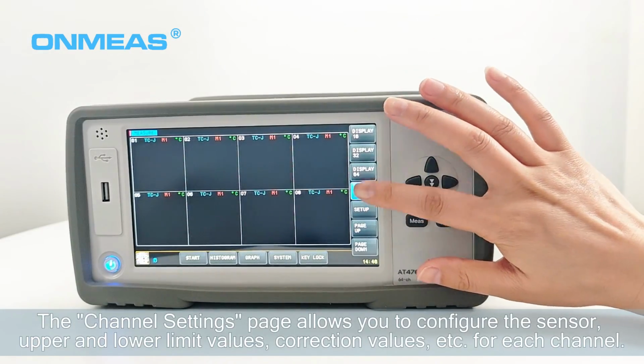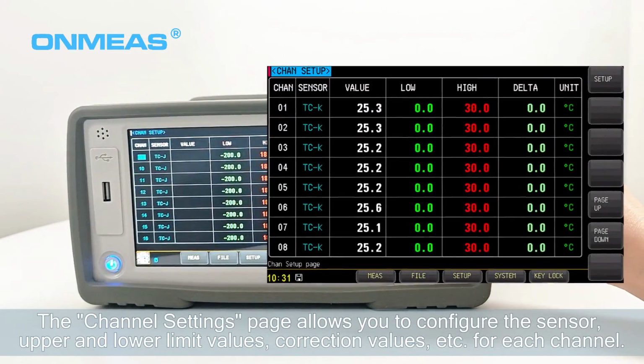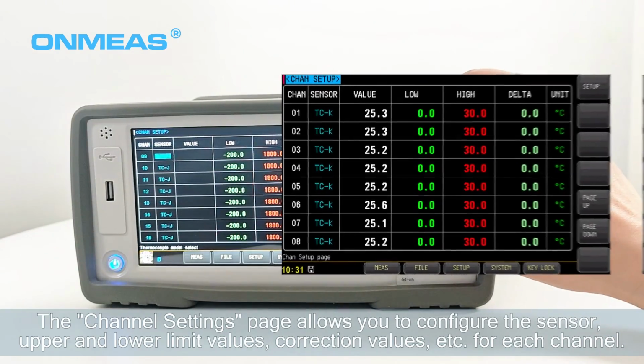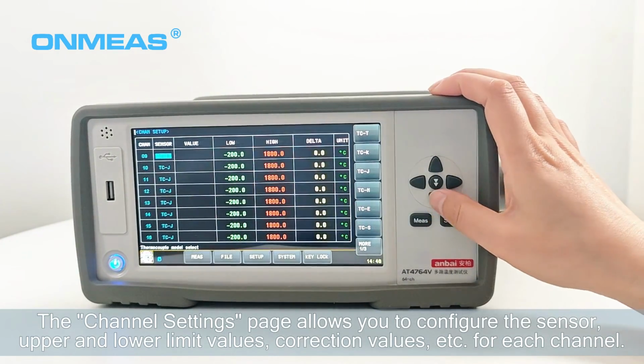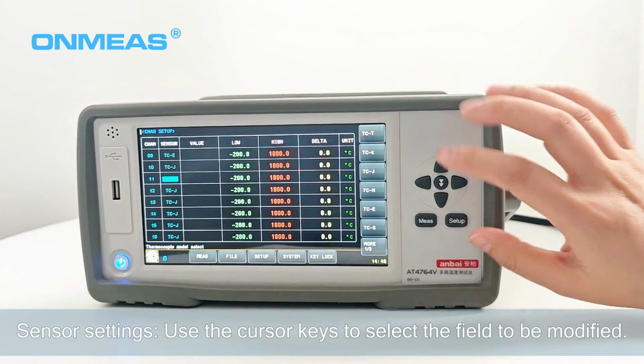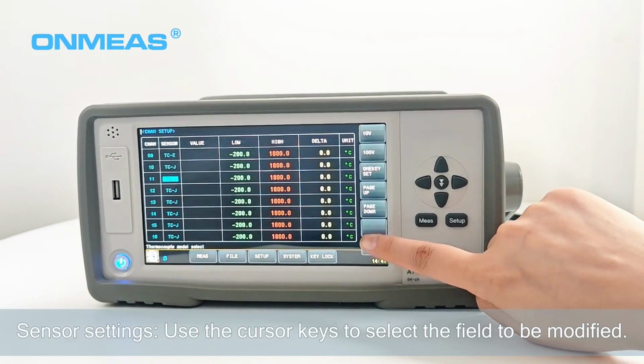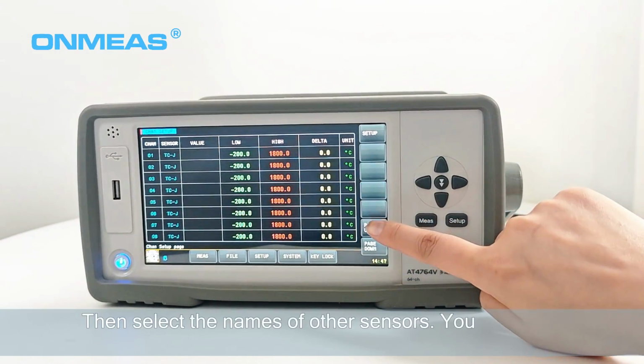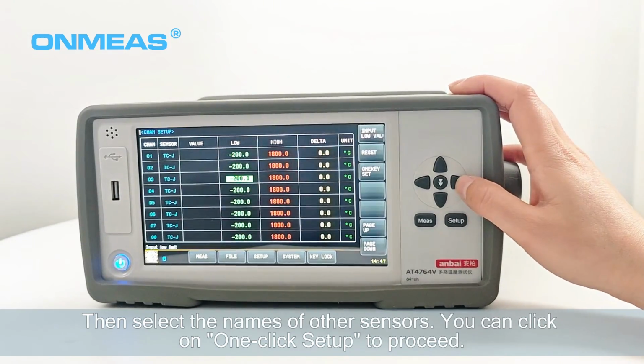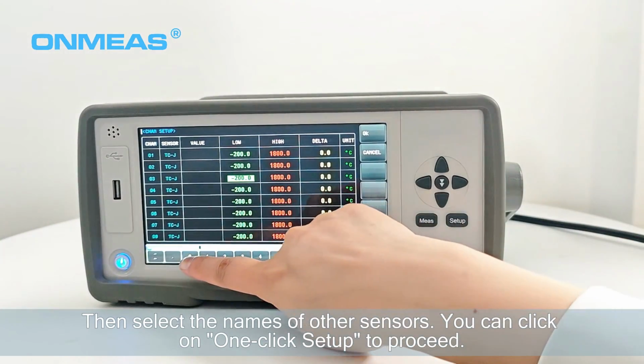The channel settings page allows you to configure the sensor, upper and lower limit values, correction values, etc. for each channel. Sensor settings: use the cursor keys to select the field to be modified, then select the names of other sensors. You can click on one-click setup to proceed.